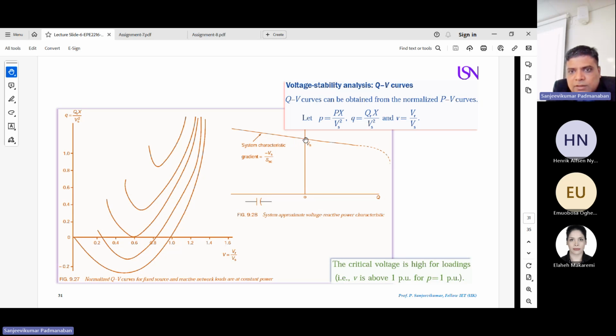at 0 Q, you'll have the maximum Vs. As Q increases, it drops down. You can have a look. Whereas on the negative side, Vs will start to increase. So the gradient is minus Vs divided by S into SC, the short circuit capacity. So you are able to calculate your gradient.